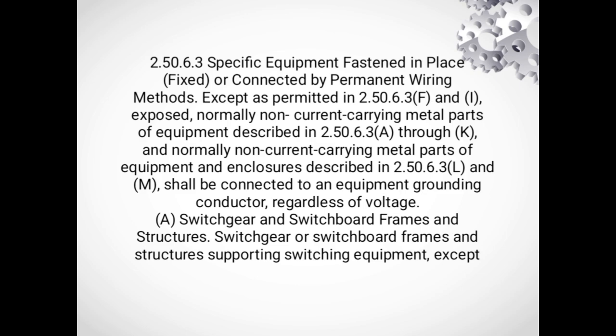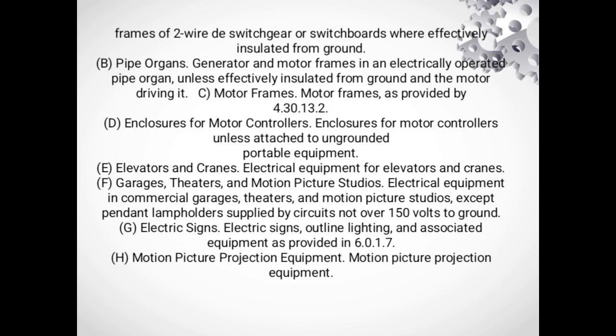2.50.6.3 Specific equipment fastened in place or connected by permanent wiring methods. Except as permitted in 2.50.6.3 F and I, exposed normally non-current-carrying metal parts of equipment described in 2.50.6.3 A through K, and normally non-current-carrying metal parts of equipment enclosures described in 2.50.6.3 L and M, shall be connected to the equipment grounding conductor regardless of voltage. A. Switchgear and switchboard frames and structures. Switchgear or switchboard frames and structures supporting switching equipment, except frames of two-wire DC switchgear or switchboards where effectively insulated from ground. B.